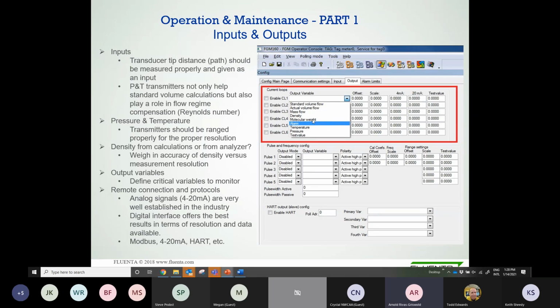We have analog and we have Modbus digital outputs. We can convert those to different interfaces. It could be a serial interface. It could be a TCP/IP interface. So this is more talking about the features we have, but just to make a point that when you're selecting a meter, you may want to take a look at your overall design in terms of the control system and everything, and do a good assessment with your flow measurement manufacturer and decide which is the best way of connecting to the DCS.